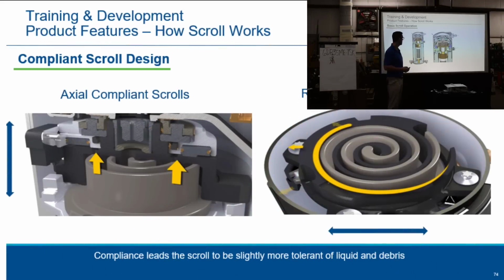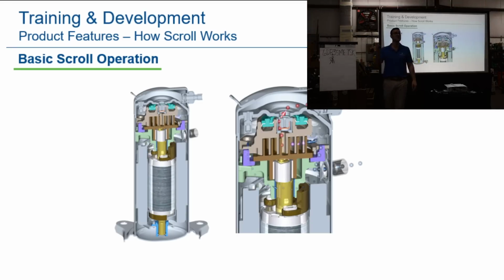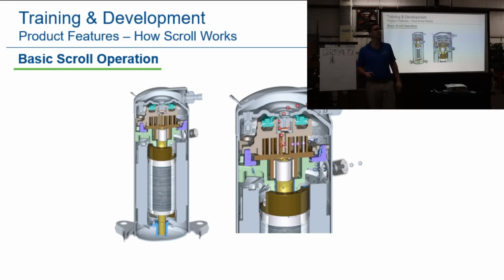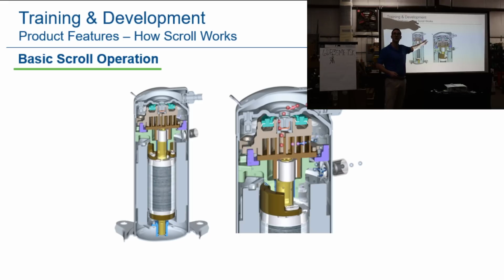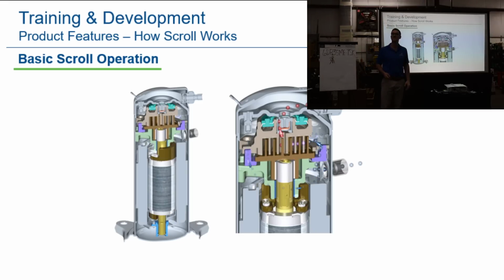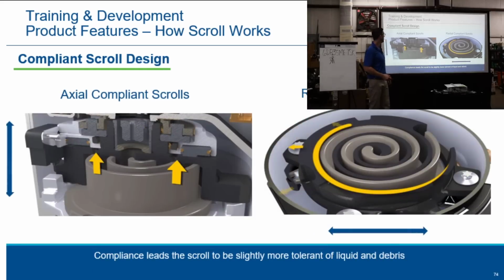Okay? And then you've got an internal pressure relief right here, depending on the model of the compressor again. Remember, we have over 20 different models of compressor. Some of them have an internal pressure relief, some of them won't. Okay, we have axial and radial compliance. This is really to protect the compressor. That means the fixed scroll will separate by 1 mil, up and down, or they'll separate radially. Some of them have a spring in them, some of them won't, and it'll separate radially if you get oil up into there.